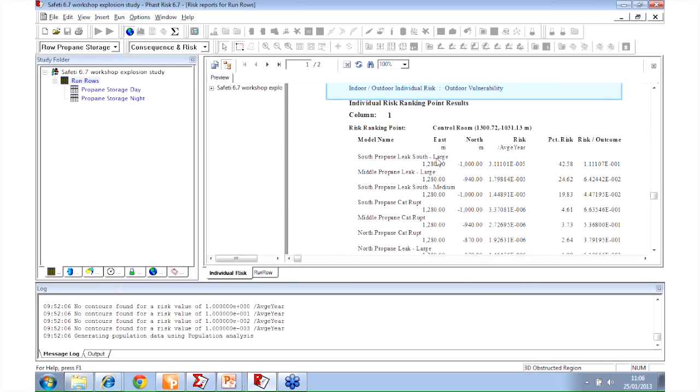You've still got an event tree following on from a large leak. So of all of this risk, what's causing the hazard? Is it what's causing the outcome? Is it a fireball? Well, sorry, these are leaks. So is it the jet fire? Is it a delayed explosion? Things like that. Depending on the kind of release you've got, there are lots of different end branches of event trees. If this was a material that was two-phase that formed a pool and a cloud, is it a flash fire, an explosion, a pool fire, the initial jet fire?